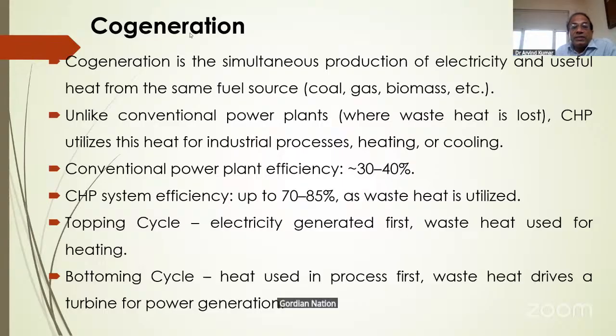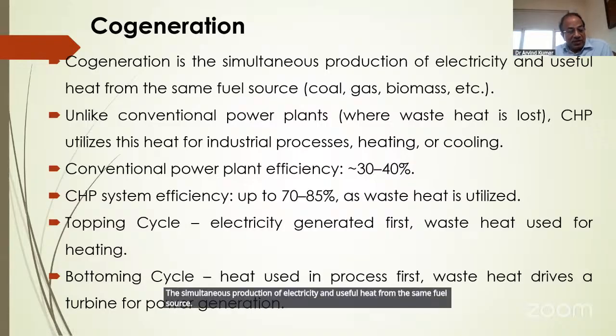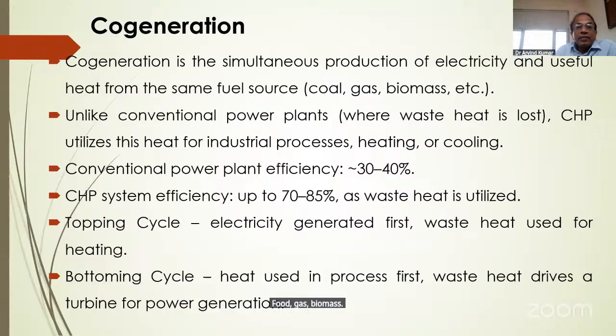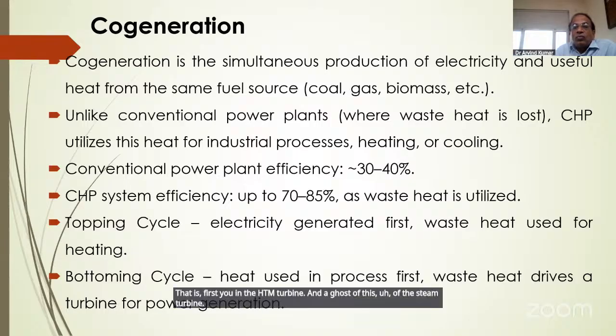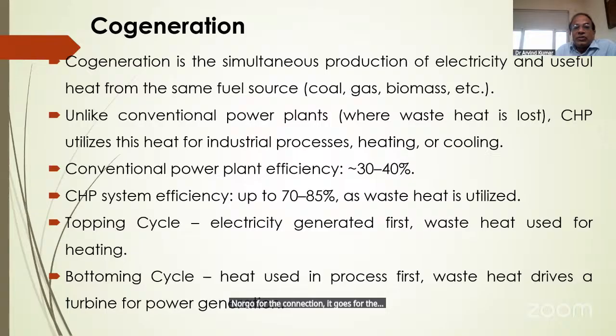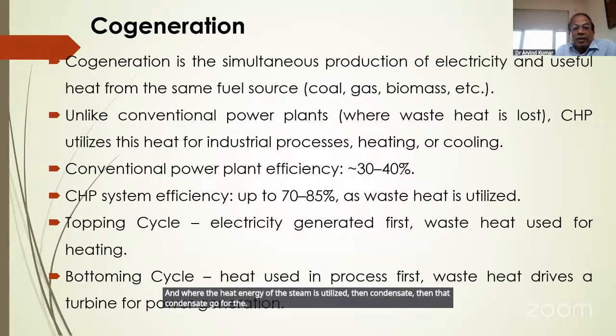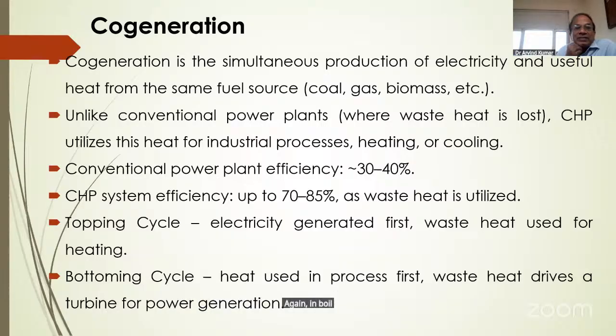Cogeneration is the simultaneous production of electricity and useful heat from the same fuel source: coal, gas, or biomass. We generate high-pressure steam that is first used in the steam turbine, and the exhaust of the steam turbine does not go to the condenser. It goes to the industrial processes, where the heat energy of the steam is utilized. Then the condensate goes back to the boiler. Such a process is called cogeneration.